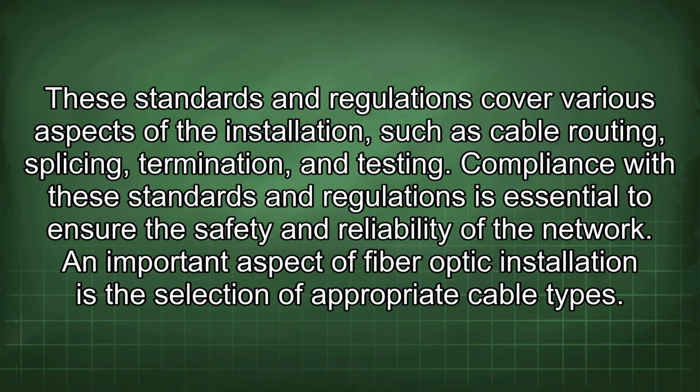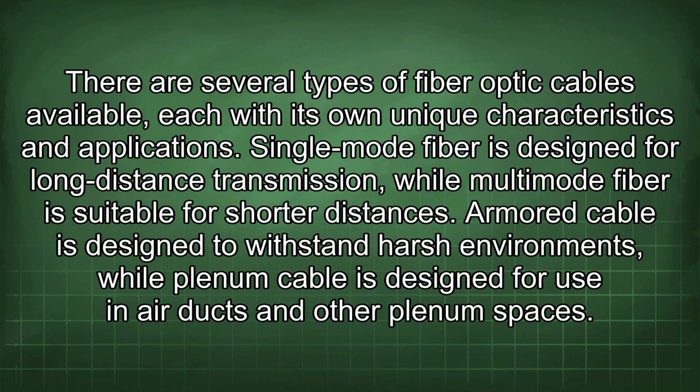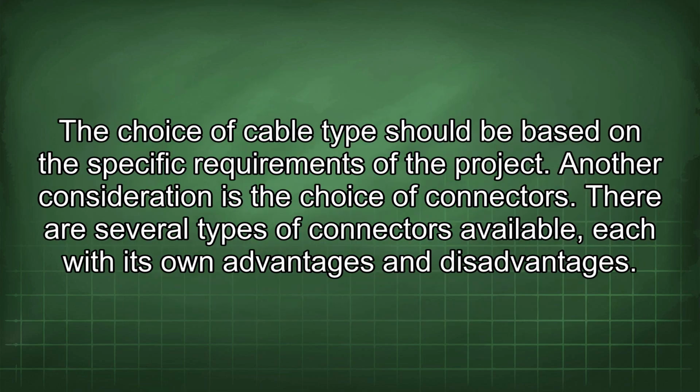An important aspect of fiber optic installation is the selection of appropriate cable types. There are several types of fiber optic cables available, each with its own unique characteristics and applications. Single-mode fiber is designed for long-distance transmission, while multi-mode fiber is suitable for shorter distances. Armored cable is designed to withstand harsh environments, while plenum cable is designed for use in air ducts and other plenum spaces. The choice of cable type should be based on the specific requirements of the project.